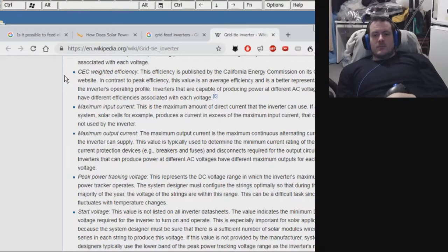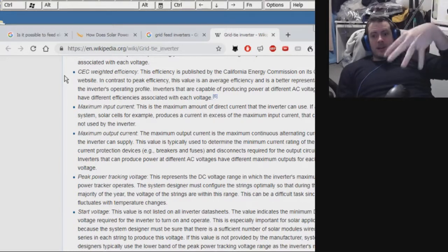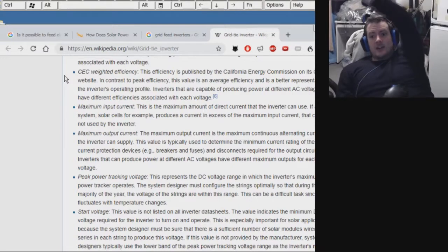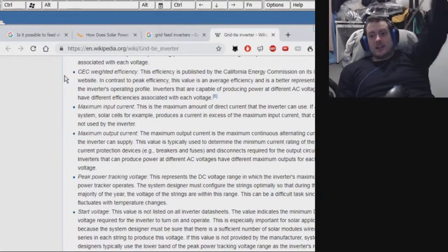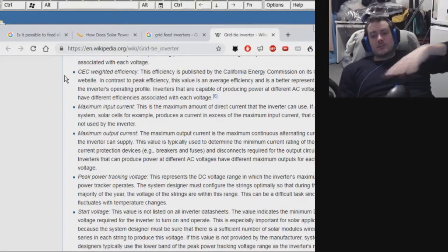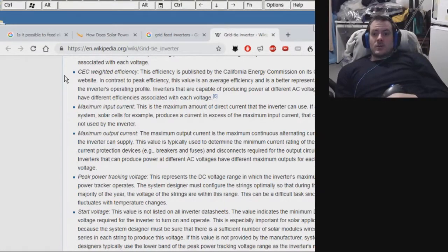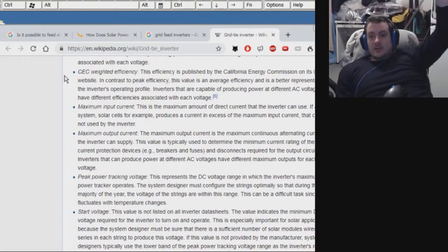Each circuit of your house has a breaker for either 15 amps or 20 amps. If you're feeding into it, your inverter will supply every appliance plugged into your circuit first. Once those are met, it'll backfeed up through the breaker in reverse and start feeding other circuits in the house. As long as that backfeed to other appliances not on your circuit stays below 15 amps, it won't blow the breaker - but it would blow as normal, just in reverse. The breaker works in reverse or forward since it has no polarity; it just switches if it detects a certain amount of amps passing through. So if my system tried to produce more than 15 amps, the breaker would blow in the garage and I'd have to reset it - so there's really no fire hazard as far as overdoing what the line for my circuit can handle.